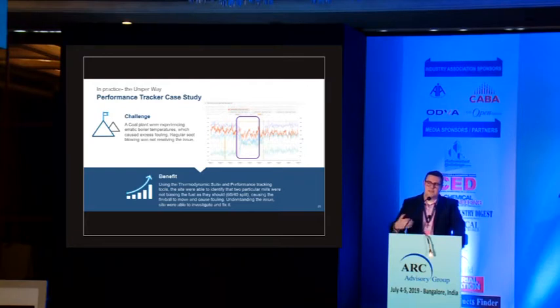They should have been biasing it 60% towards the bottom, 40% to the top. What they were actually doing was closer to 70% to the top, and that was causing the fireball in the boiler to move and causing the excess fouling.